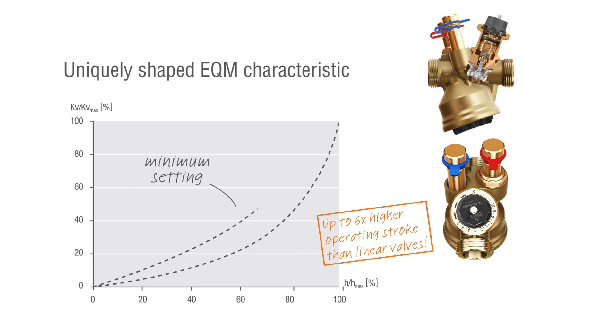Therefore, TA modulator is able to precisely control also very small flows. The characteristic remains equal percentage within the range of maximum and minimum flow setting.